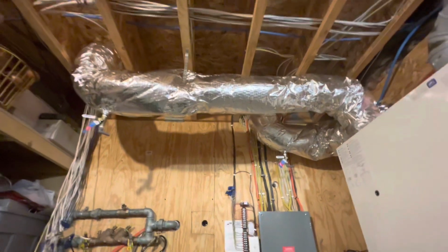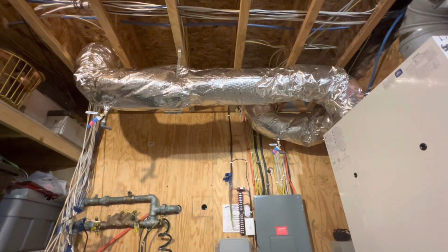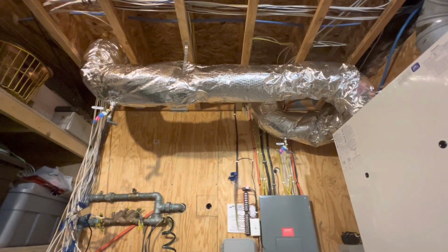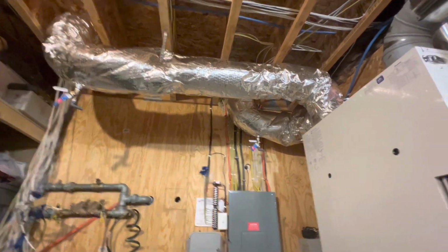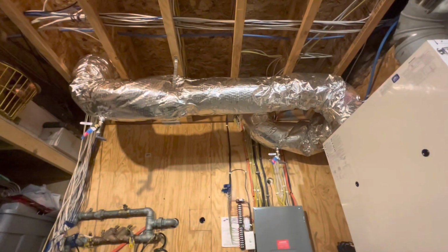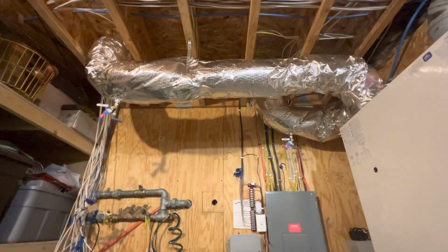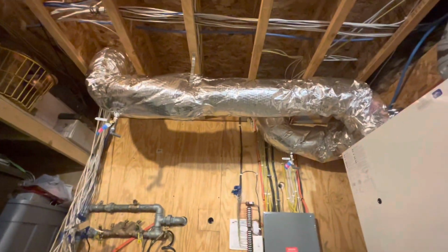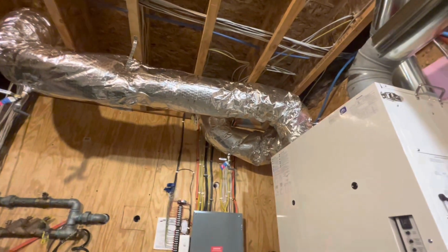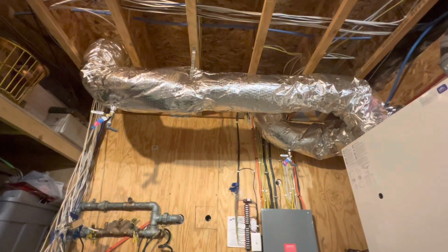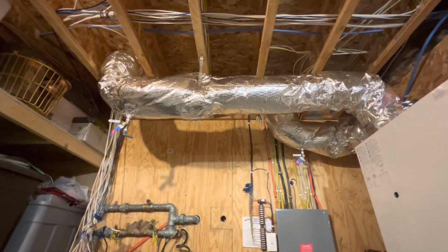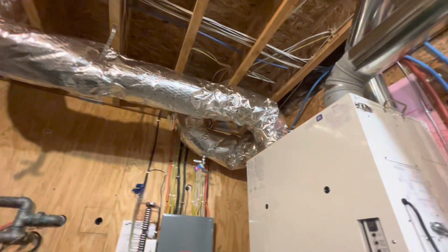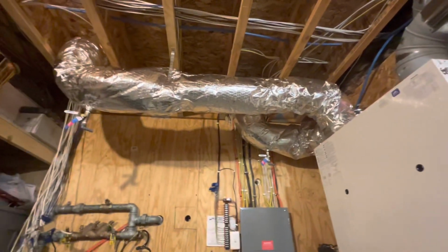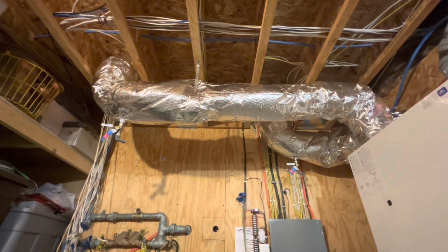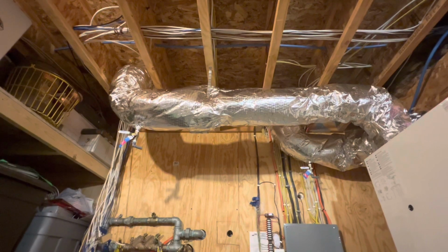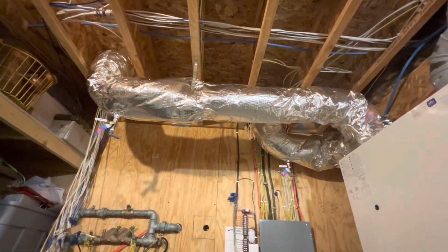Then I went ahead and insulated it with, I think, R7 or R9 insulation with a vapor barrier in it. After I installed the unit, I started it up and ran it for a few days. I didn't have this insulated, and it was wintertime, so condensation obviously formed on the cold side because those pipes were at the outside temperature, so they got condensation built up on them. So the purpose of the insulation is to keep condensation from forming on those lines and keep a vapor barrier, so you don't have any areas where air can get in contact with that cold pipe.